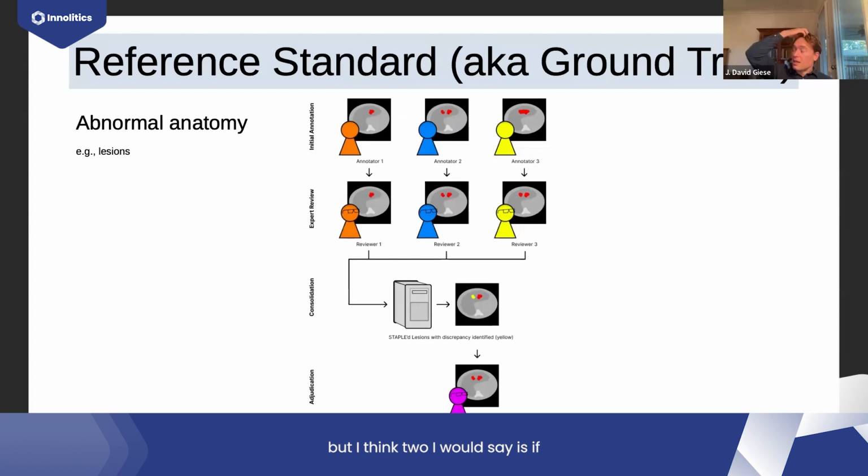But I would also say, if there's some site-specific variability or situation where you think the results would be unfavorable, it would definitely help you if you documented that in your protocol, and usually in the pre-sub you would explain the criteria we would use to say this site isn't appropriate. I think this was on an IVD project that we weren't running the study or doing the strategy in at all.